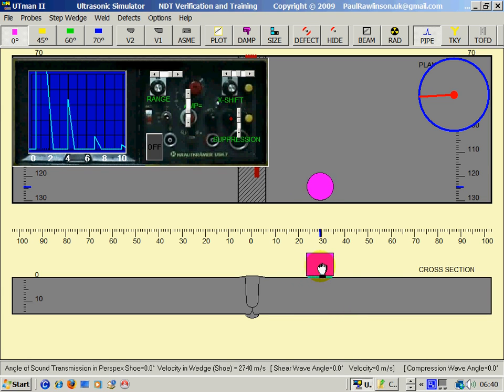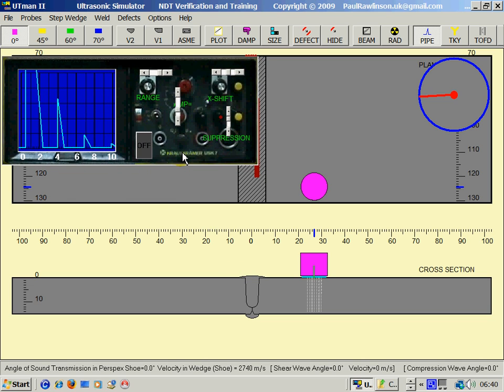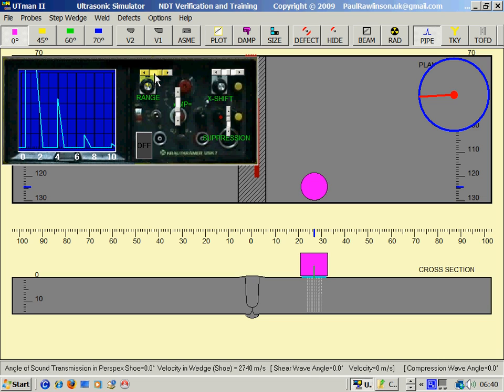Using the zero probe we can measure wall thickness or check for laminations. On the USK7 we can change the range of the UT set by clicking on the range bar here.